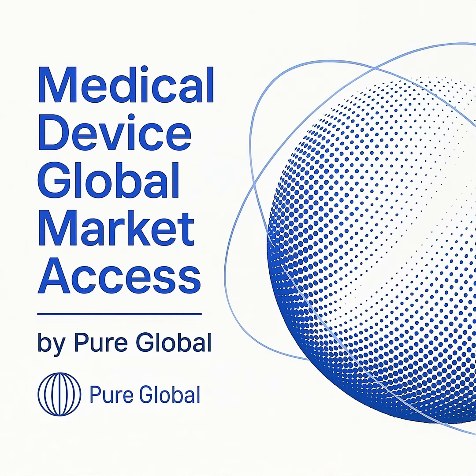This includes devices intended as implants, those used for supporting or sustaining human life, or devices of substantial importance in diagnosing or treating disease. For an SR device, the sponsor must submit a full IDE application to the FDA and receive formal approval from both the FDA and an Institutional Review Board, or IRB, before a study can begin. Conversely, a non-significant risk, or NSR, device study does not require the submission of an IDE application to the FDA. These studies are considered to have an approved IDE as long as the sponsor complies with abbreviated requirements.